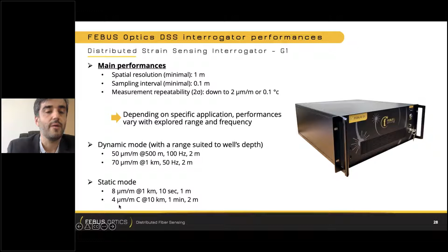On static mode, you can be much more accurate, even with 1 meter of spatial resolution. With a 10-second measurement at 1 kilometer, you can be at 8 microstrain, even 4 if you wait 1 minute with 2 meters of spatial resolution at 10 kilometers. So all the parameters are interdependent, but you can reach high frequency or high sensitivity in terms of strain. So it can be provided with 16 channels as well as the Raman DTS. And one unique feature is one channel can be dynamic, meaning at several tens of hertz up to 100, as seen before. And you can go even up to 4 dynamic channels on demand.